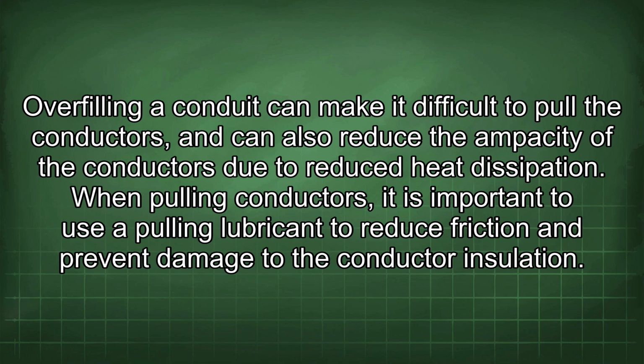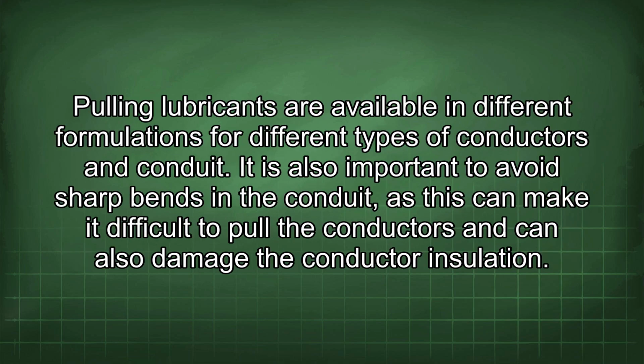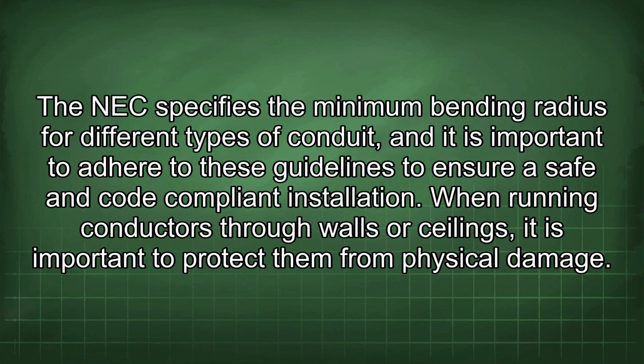When pulling conductors, it is important to use a pulling lubricant to reduce friction and prevent damage to the conductor insulation. Pulling lubricants are available in different formulations for different types of conductors and conduit. It is also important to avoid sharp bends in the conduit, as this can make it difficult to pull the conductors and can also damage the conductor insulation. The NEC specifies the minimum bending radius for different types of conduit, and it is important to adhere to these guidelines to ensure a safe and code-compliant installation.